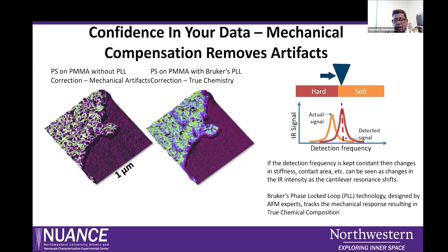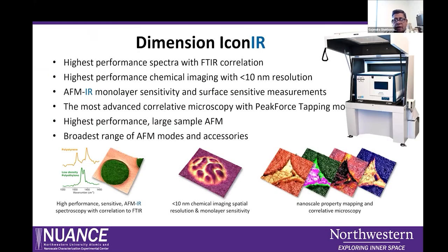So the Dimension IconIR we have is pretty much the AFM that you are using. It's an 8-inch stage here, but otherwise it's exactly the same, the high performance spectra with FTIR correlation. You can go down to even 5 nanometer spatial resolution, and also spectral resolution in the case of tapping mode IR. It's monolayer sensitive. And then you can also do correlative microscopy. That's one of the advantages here.